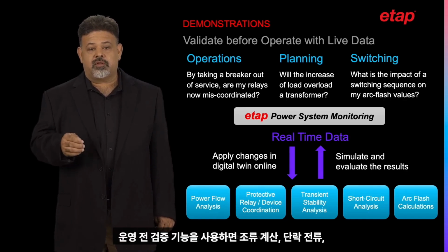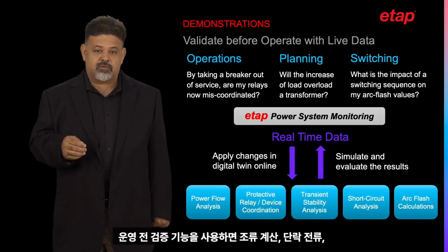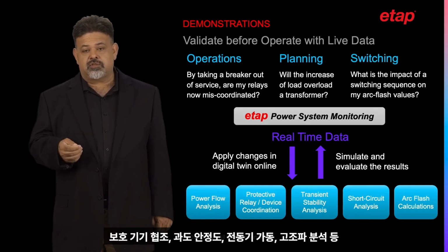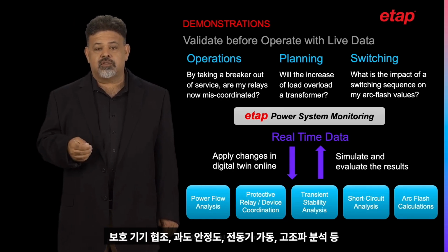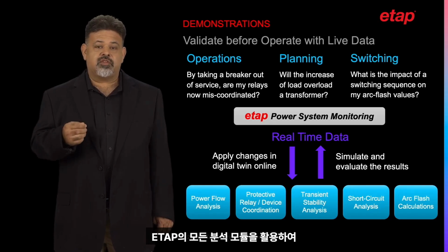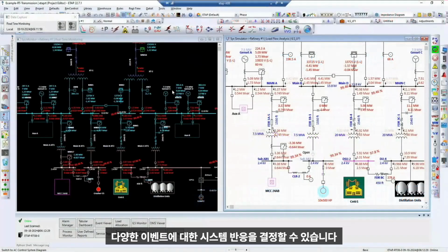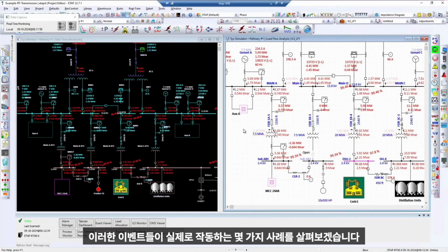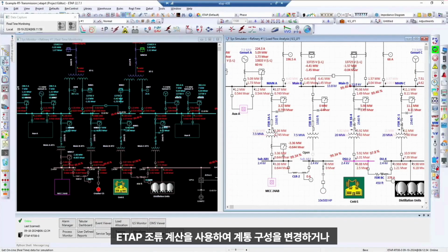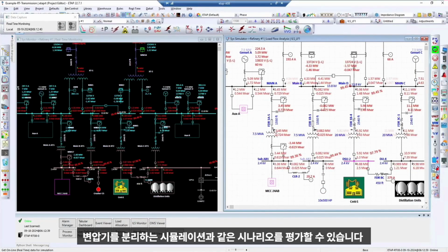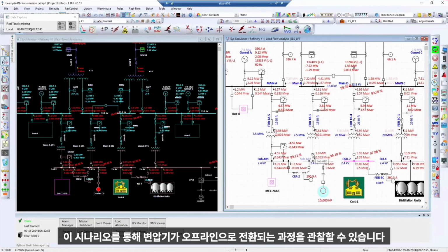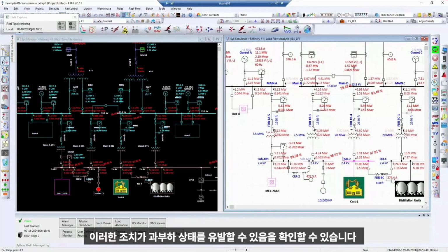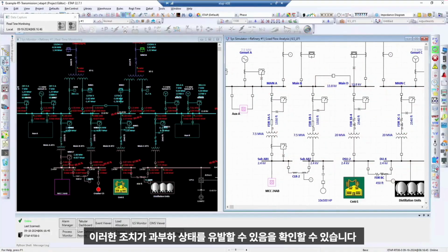Using Validate Before Operate, you can utilize any of the full spectrum of analysis modules in ETAP, such as load flow, short circuit, protective device coordination, transient stability, motor acceleration, harmonics, and more to determine the system response against different events. Let's take a look at a few examples of these events in action. Using ETAP load flow, you can evaluate scenarios such as changing the topology and simulating bringing down a transformer. From this scenario, we can observe as a transformer is being brought offline. When we open the required breakers, we notice that this possible action will create an overload condition.